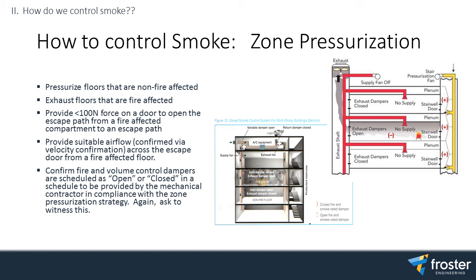Pressurized floors that are non-affected, exhaust floors that are. This is the key element. So if you're trying to get out of the floor, you want to make sure that the pressure behind the door, the escape door, is no greater than 100 newtons. You don't want to make it difficult to get out of the building. So that force is translated based on the pressure differential. So again, you can allow a 20 to 80 Pascal difference between affected and non-affected zones.